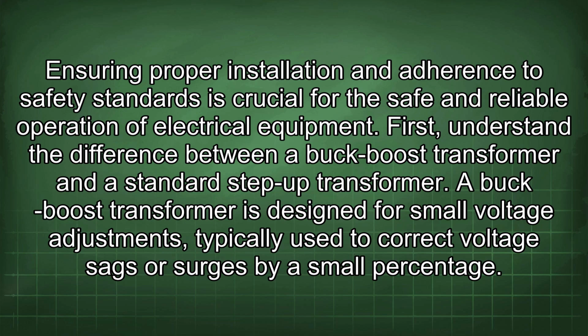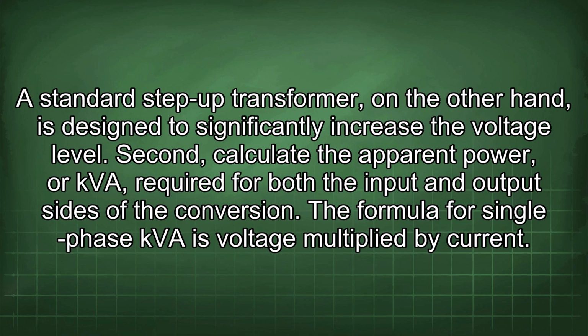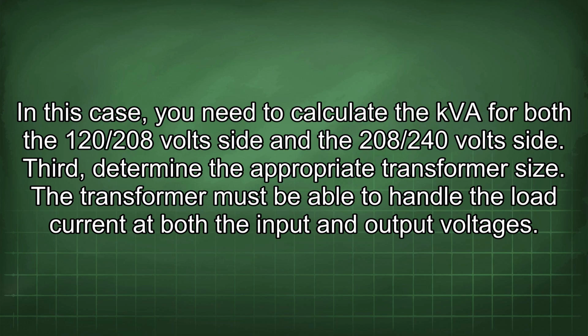First, understand the difference between a buck-boost transformer and a standard step-up transformer. A buck-boost transformer is designed for small voltage adjustments, typically used to correct voltage sags or surges by a small percentage. A standard step-up transformer, on the other hand, is designed to significantly increase the voltage level. Second, calculate the apparent power, or kVA, required for both the input and output sides of the conversion. The formula for single-phase kVA is voltage multiplied by current. In this case, you need to calculate the kVA for both the 120/208 volt side and the 208/240 volt side.